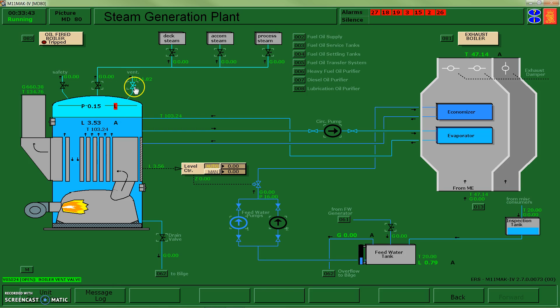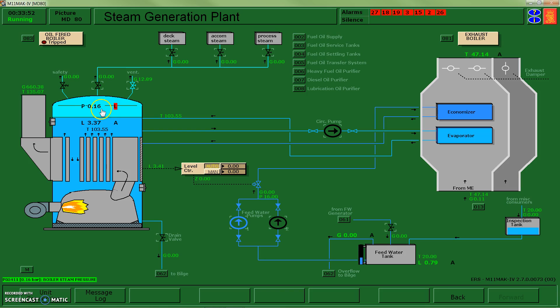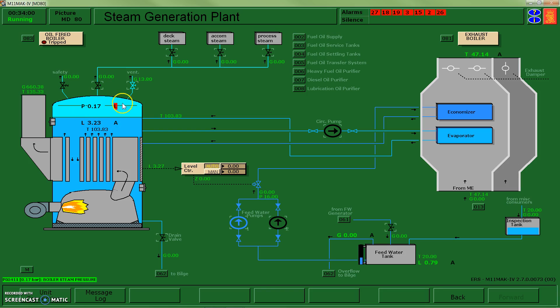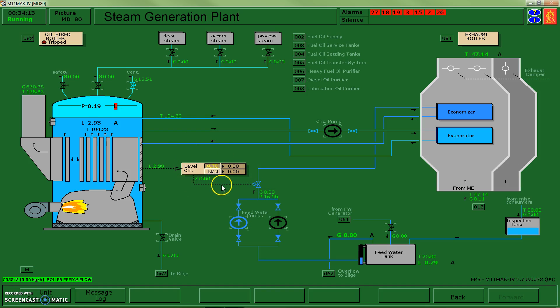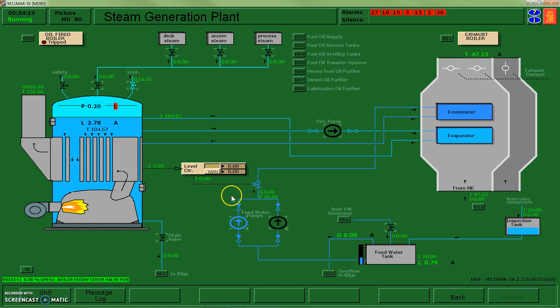So I'm going to let that run for a bit, say bring my pressure up to about 1 bar or 15 psi. And that should probably be enough time and enough volume of steam that's been displaced. You can see my level's starting to drop now that I'm making some steam. And I can just verify at this point that my pump is on, my level controller is in auto, and it should start to turn itself on or open up that valve shortly.